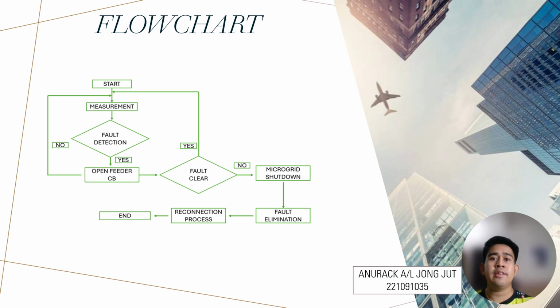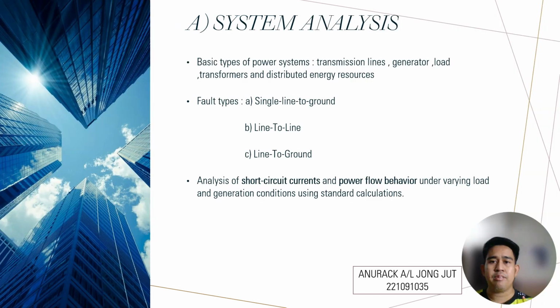When the fault clearance is not available, we should do the microgrid shutdown. Then next we proceed to the fault elimination, then the reconnection process and end. So this is roughly our main flowchart for this title. Okay, next is the method for adaptive power protection.